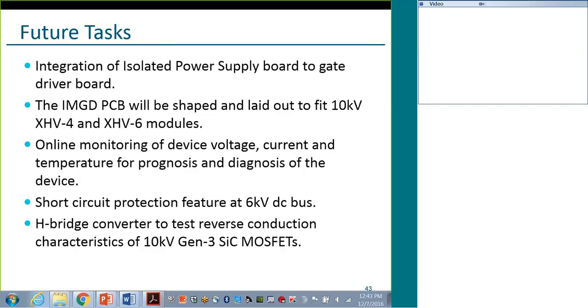Yeah, so for these modules that we had, we do have a temperature sense in the module, a thermistor in the module itself, and we're getting feedback from there. The important thing is that we are isolating it through the gate driver such that we can optically transmit it to the interface board. So right now there is a temperature sense, and because we do have a CPLD, we are going into actually estimating the temperature based on the model of our package itself.